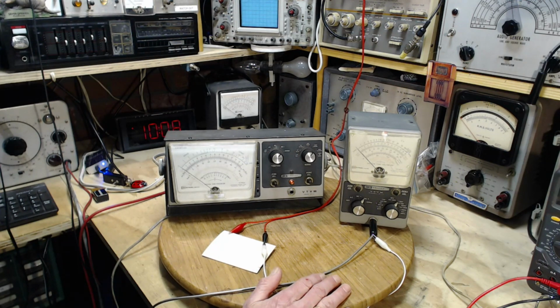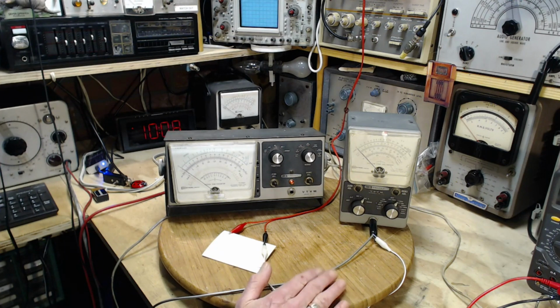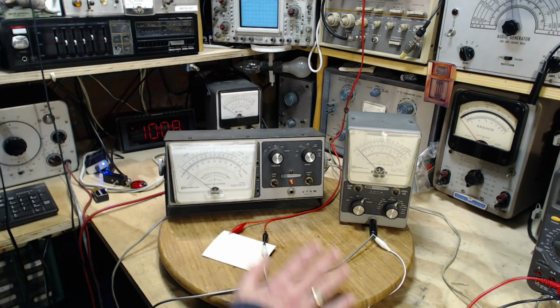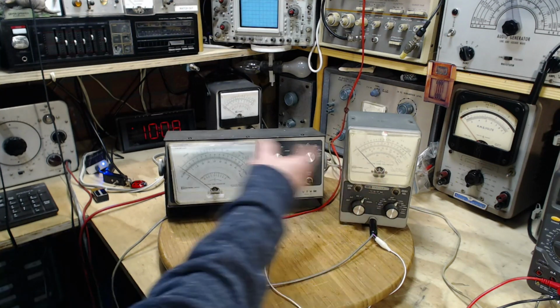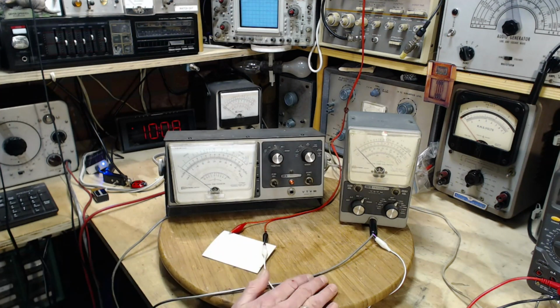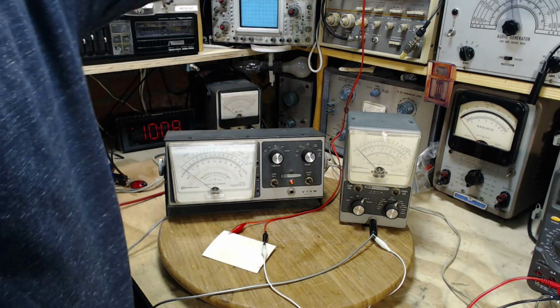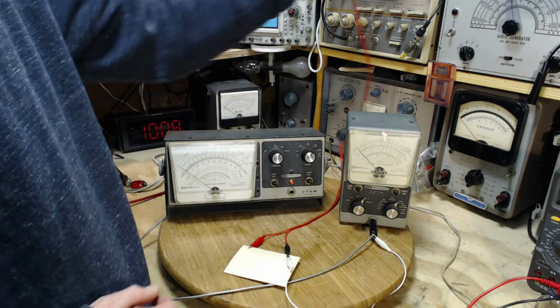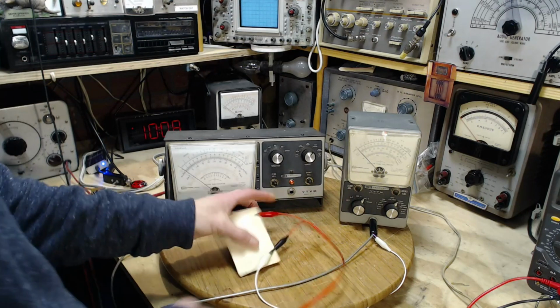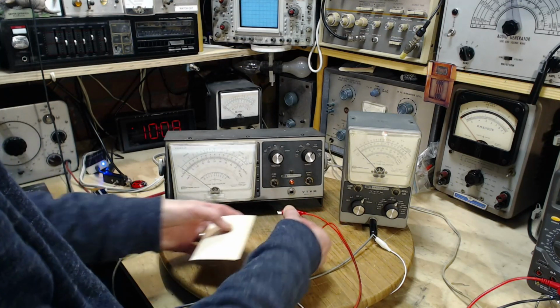Next step, I think, is checking the resistance readings. They're based on batteries that are or are not inside these. Next step is take the case off and do a general inspection of what's inside these two units, and then plan out the next step, which is to turn off the high voltage. That's really the next step. Pull these out of here. That's really what I should have done immediately upon finishing that test. Good though. So that's what I'll do.